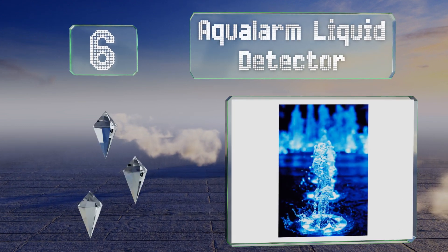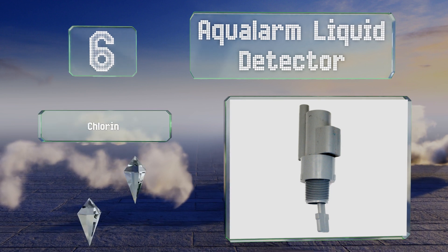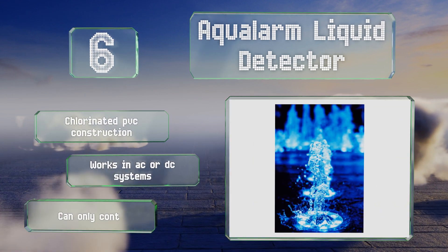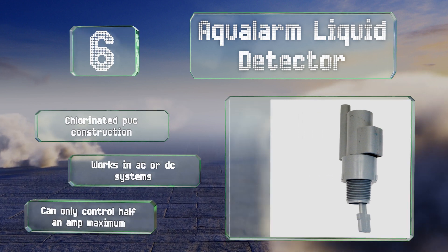Starting off our list at number six, the affordably priced Aqualarm liquid detector can be attached to a three-quarter inch T or a reduction T as large as one and a half inches. This epoxy-sealed unit can be wired up to a simple on-off indicator or a contactor capable of controlling heavier loads. It's a chlorinated PVC construction that works in AC or DC systems, however it can only control half an amp maximum.